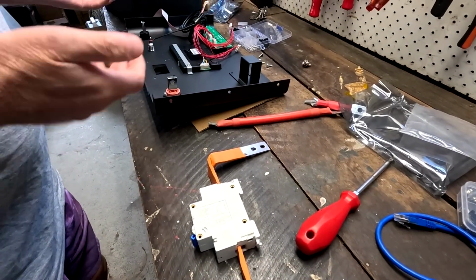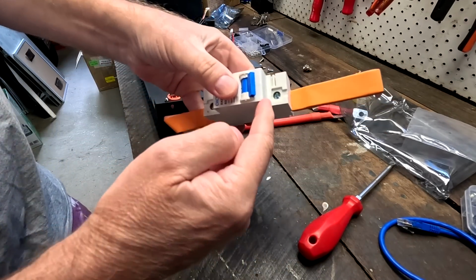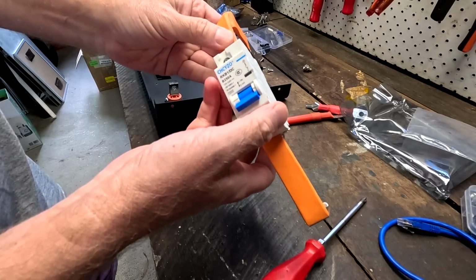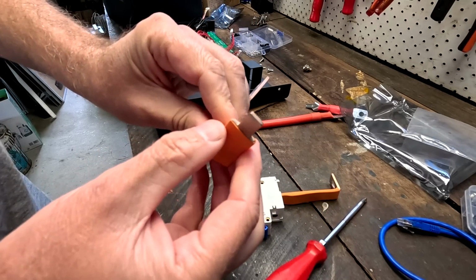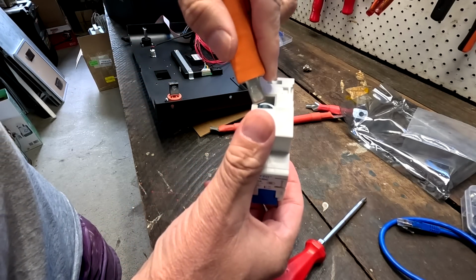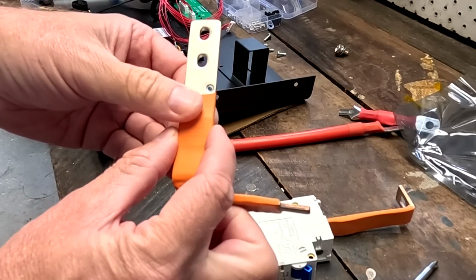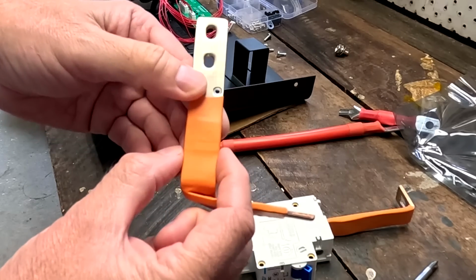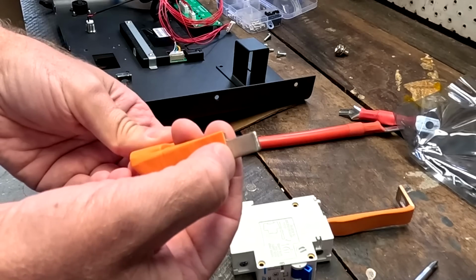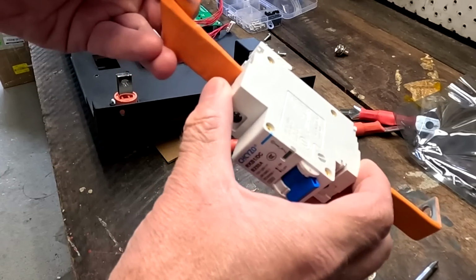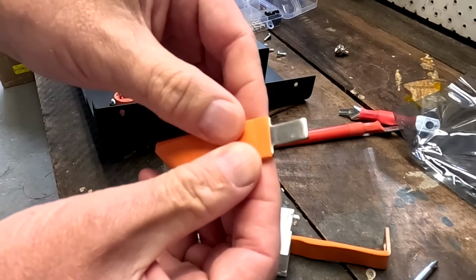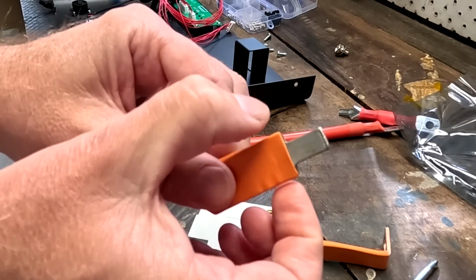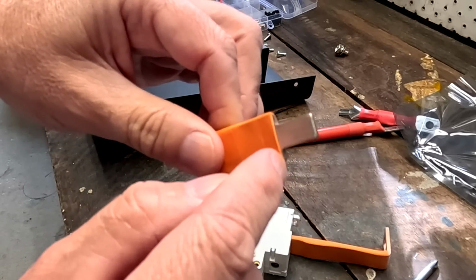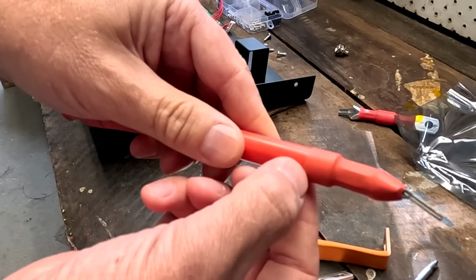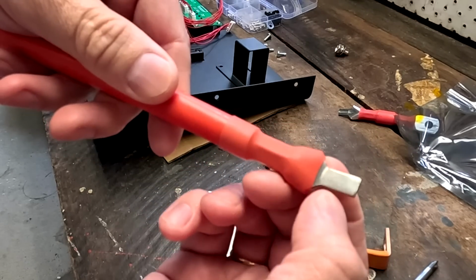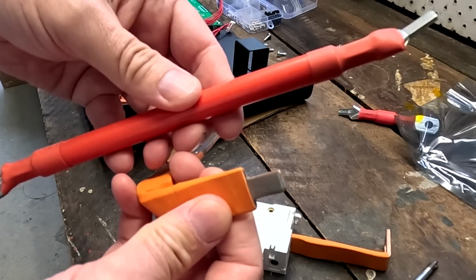To make this all work, we have to disassemble the circuit breaker again, otherwise we cannot access the terminal screws. Before I finalize this, I want to get your thoughts on one thing: this bus bar has been narrowed down to fit the actual circuit breaker terminal, so we're using only half of the bus bar area where it connects to the breaker. If this is a 200 amp bus bar, we'll have only 100 amps of material connecting to the breaker. Is this a concern? Should they have folded the bus bar into one thicker connector instead, so we stay with the full area and diameter of the conductor? I don't think this is the correct way of doing it - it's like using a flexible cable and cutting away some strands to fit a smaller bootlace. You're basically reducing your effective conductor size.